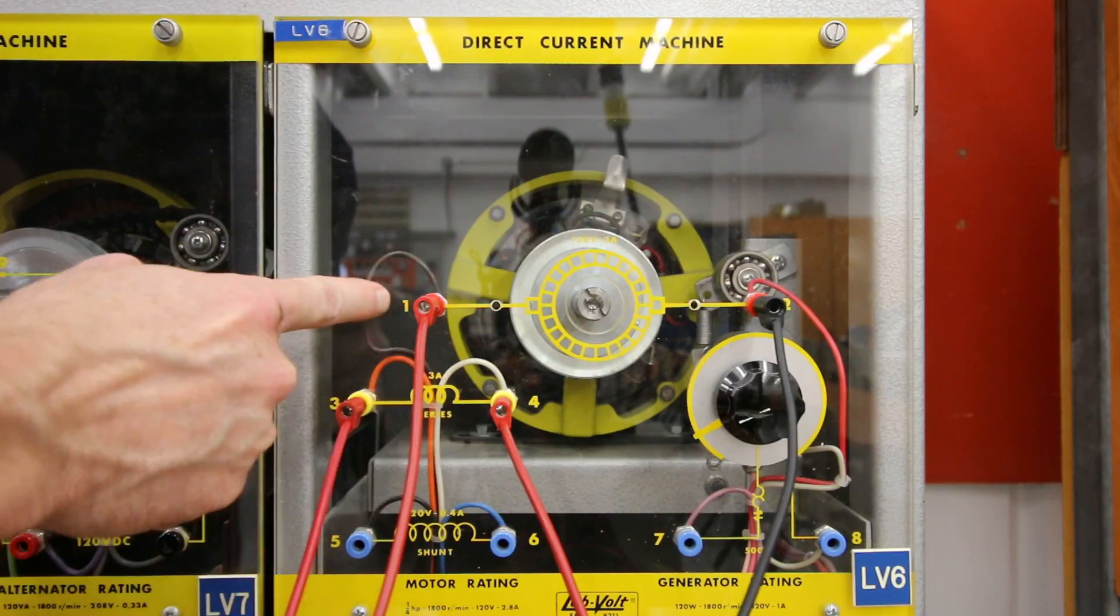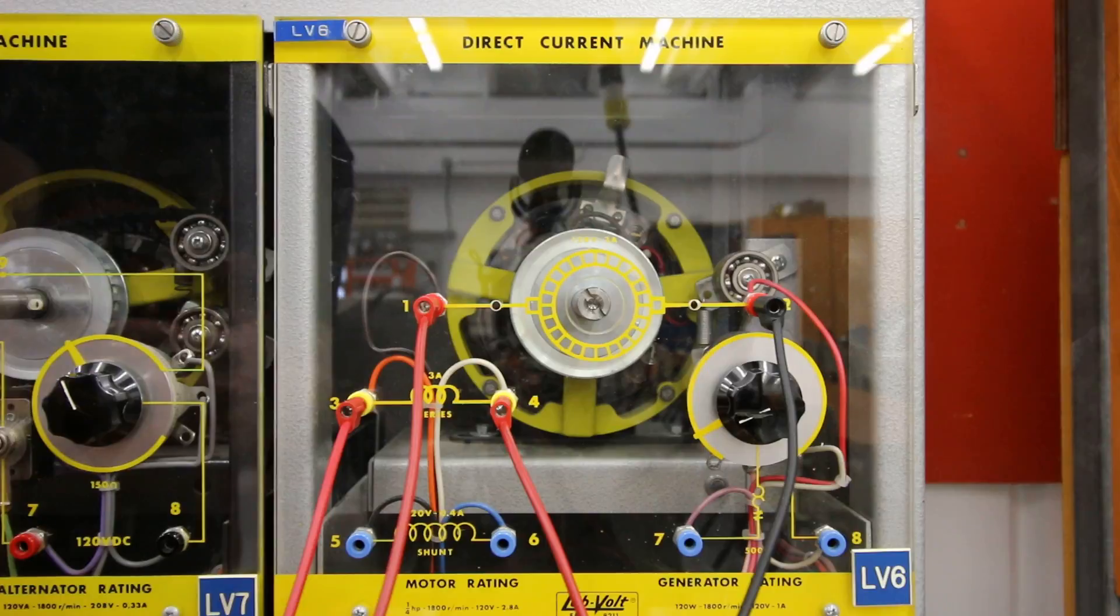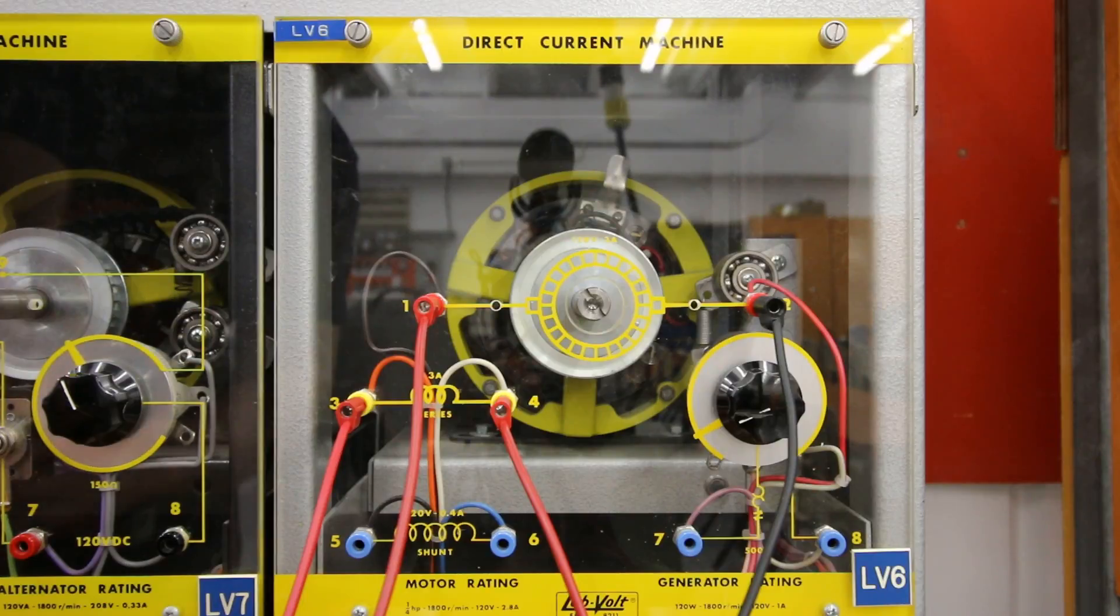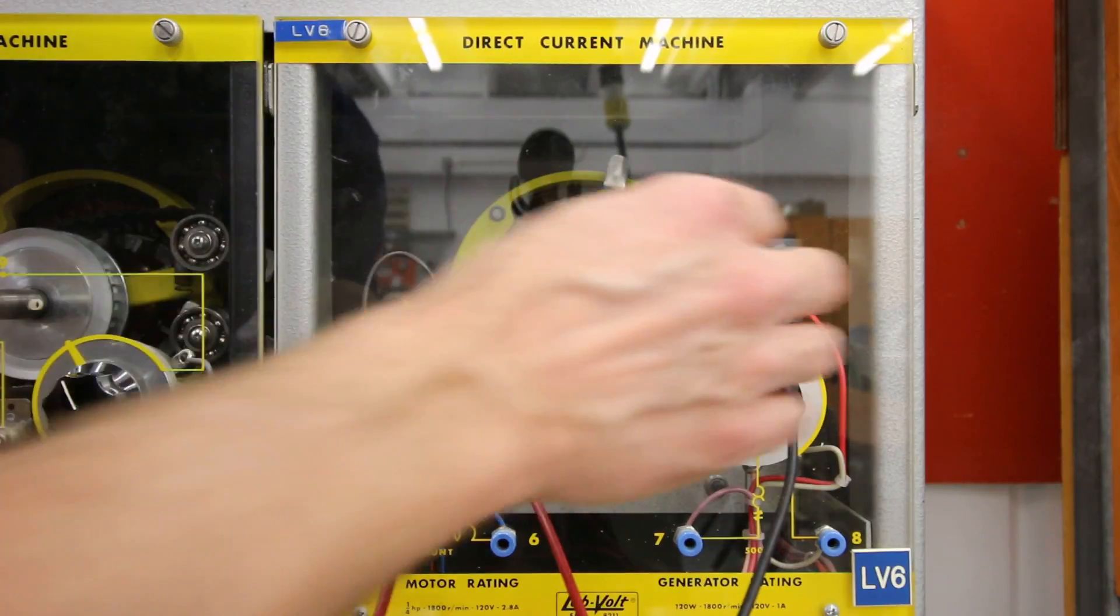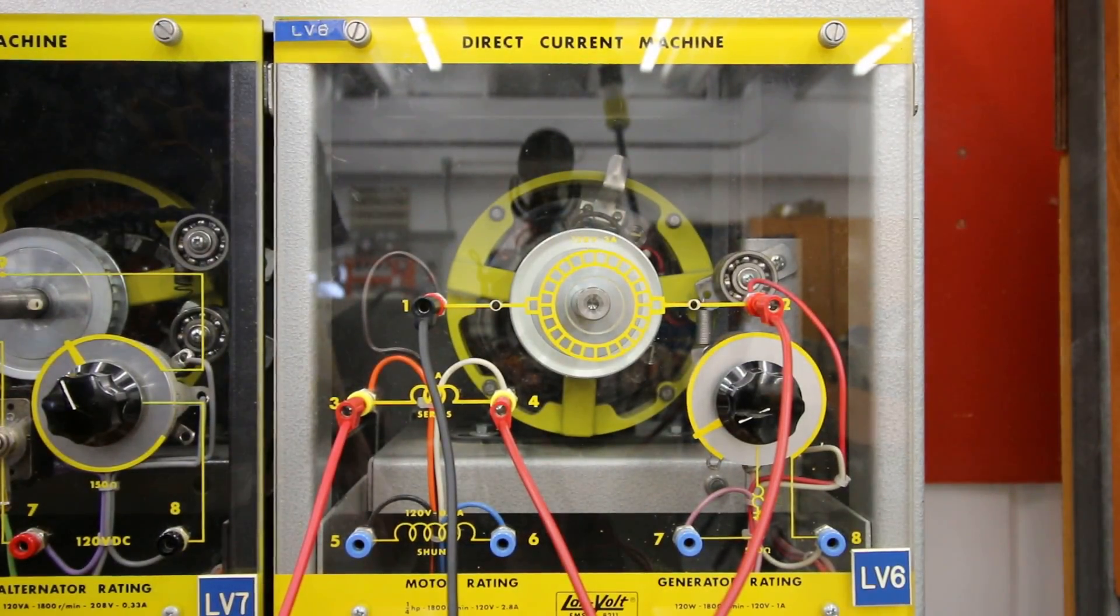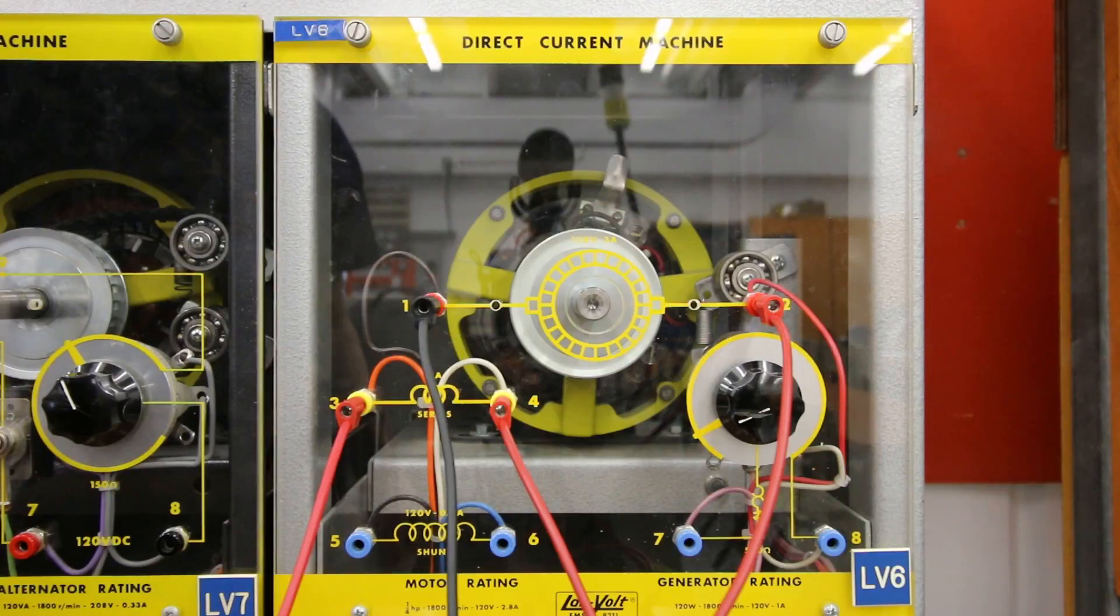Because we don't know which one is S1, S2, A1, A2, we're just arbitrarily making connections and seeing which way it spins. This one is going in a clockwise direction. If I want to get this motor to go in the opposite direction, I can simply just change my A1 and A2.